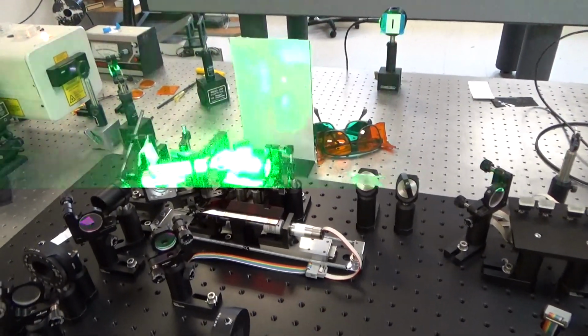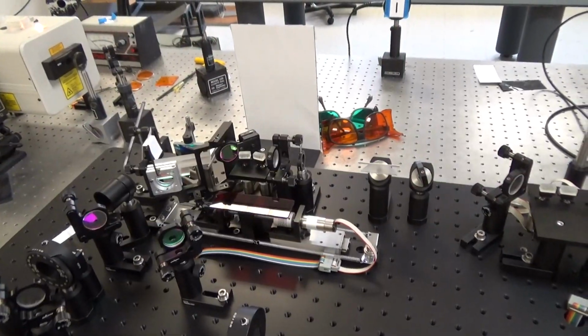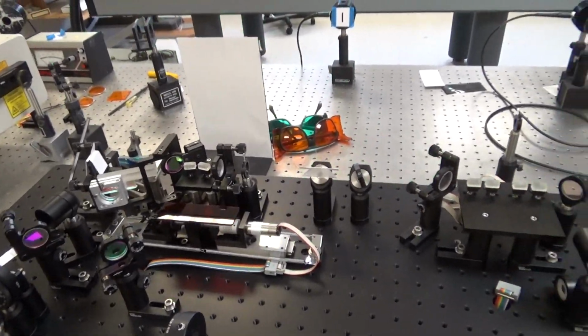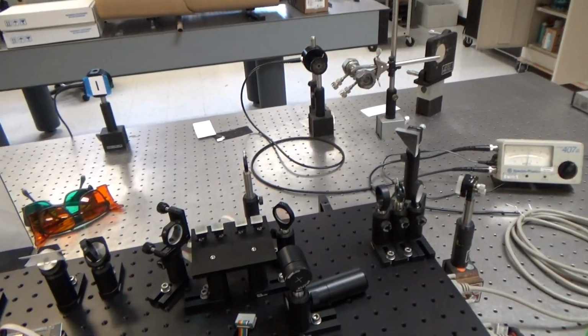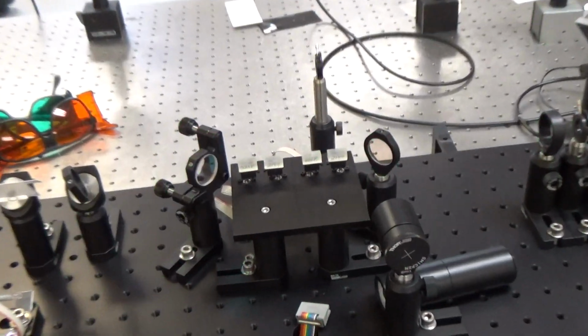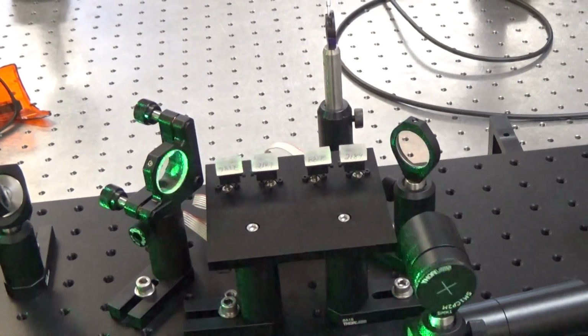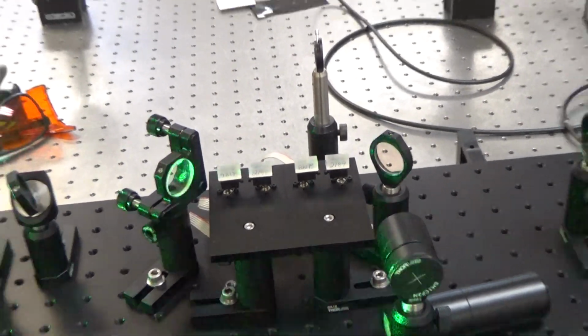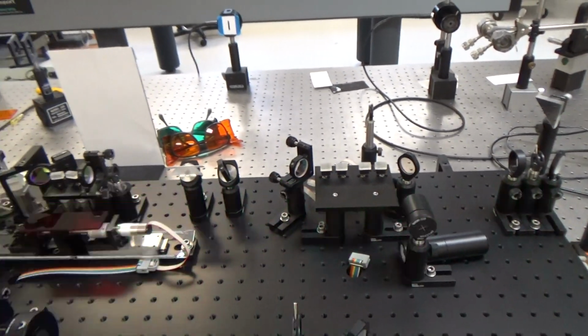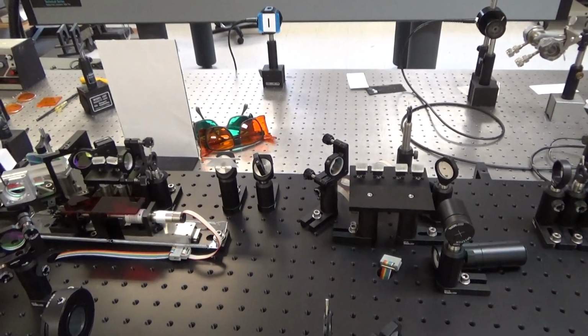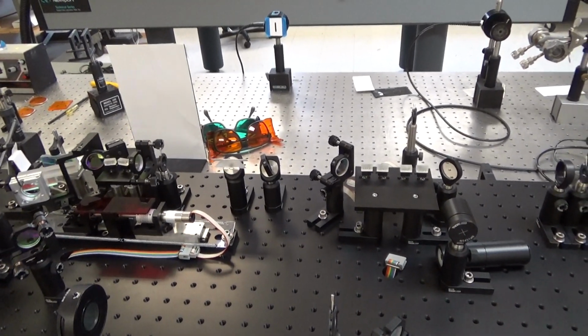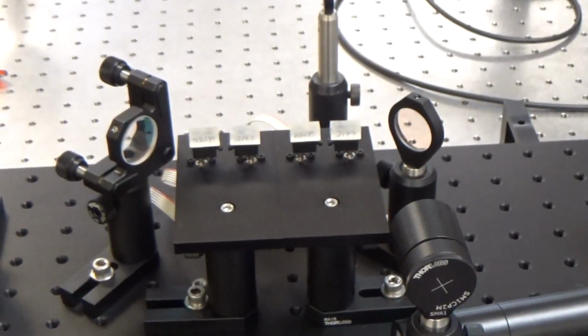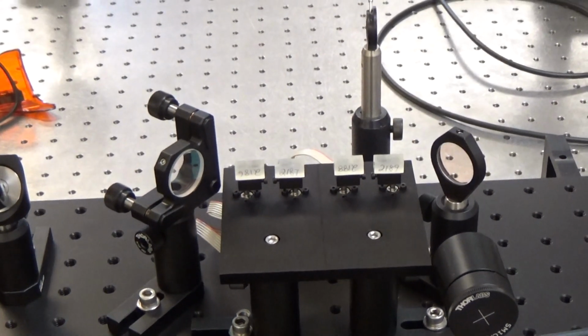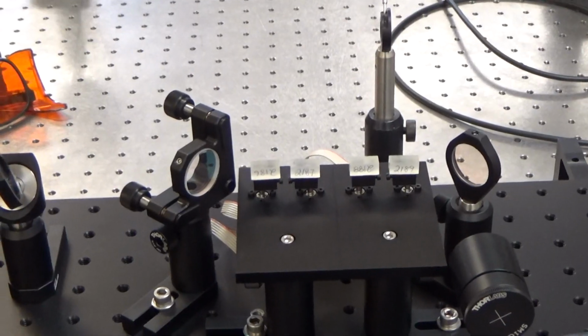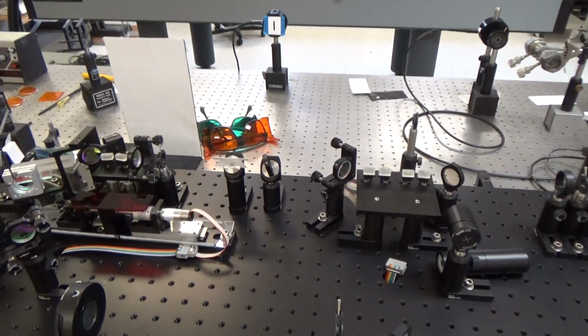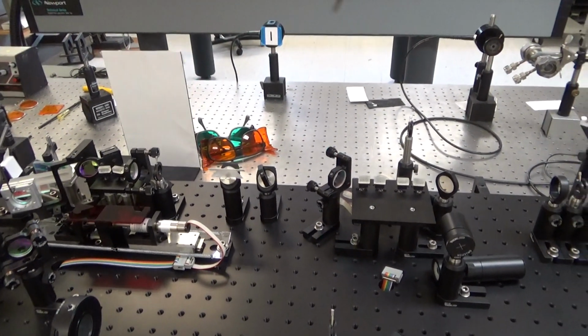Okay, at this point we've done the calibration for the system. We've corrected for the wavelength offset by measuring the absorption in acetylene. The last stage is to calibrate each one of the OPA crystals. Now I'll do it in the same fashion, scanning down to 710 and taking data.